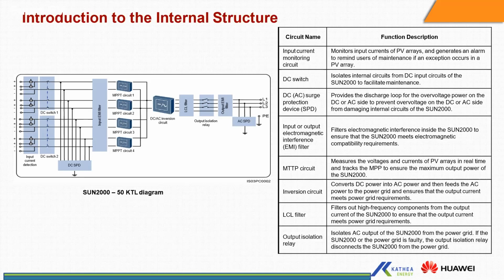Internally the system parallels those 2 strings, and then they are passed through built-in DC switches. The DC switches are split equally between the number of MPPTs for all ranges of inverters. So for the 50 and 60, which have 6 MPPTs, there are 2 DC switches. DC switch 1 controls 3 MPPTs, and the other DC switch controls the other 3 MPPTs. After the DC switches, the inverter has a built-in DC SPD, which is type 2. From there it goes to the MPPT input through the DC-AC inversion circuits. And then on the output side, the inverter also has a built-in AC SPD, which is also type 2.